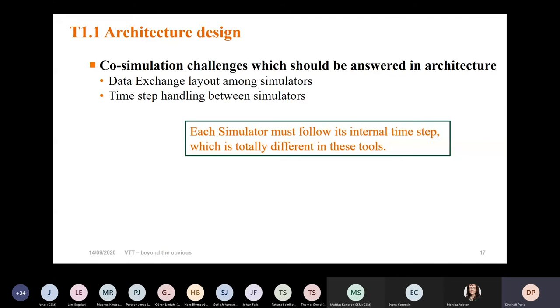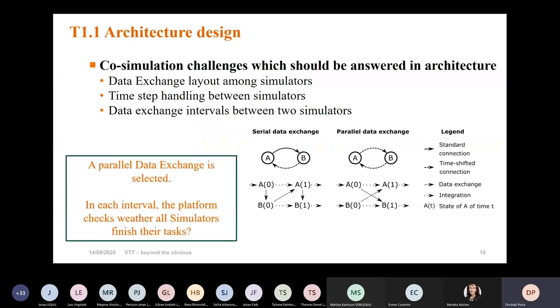There are more challenges in designing the co-simulation platform. The method we use is the open method — all different software can run simultaneously with their own time-step handling. For example, the power system can run with a much smaller time step, while the thermomechanical system may need only one second for many phenomena. Each software handles these things independently, but they share a data exchange interval between the two simulators.